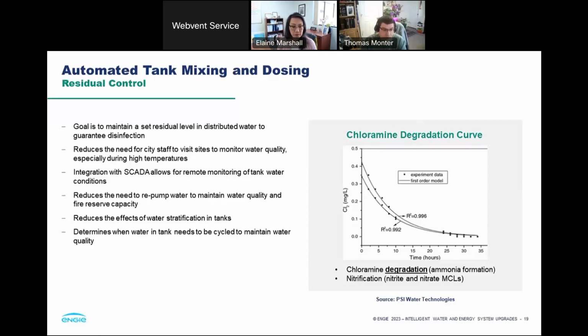The SCADA system allows them to monitor each of those systems. In this case, SCADA only monitors the local control systems because of risks - everyone has heard of the problems with cybersecurity attacks, and that was one of the primary goals of the SCADA system, to make sure the city's subsystems were not vulnerable to those types of attacks. So this is a monitor-only situation where changes to those systems cannot be done remotely; they have to be done locally.